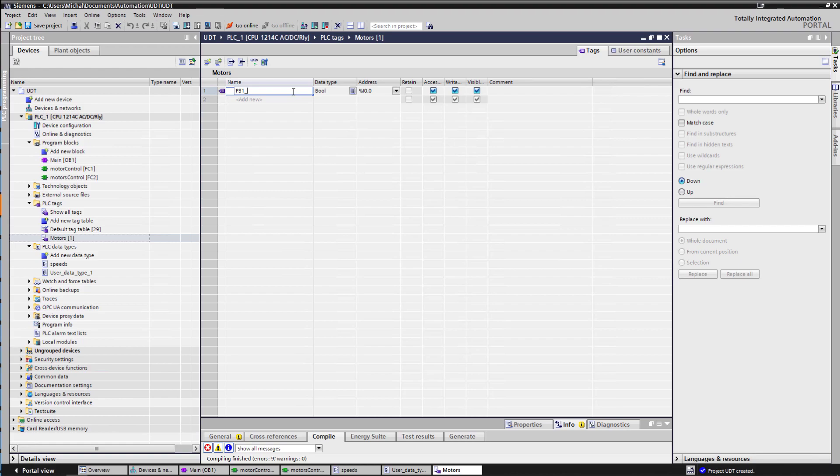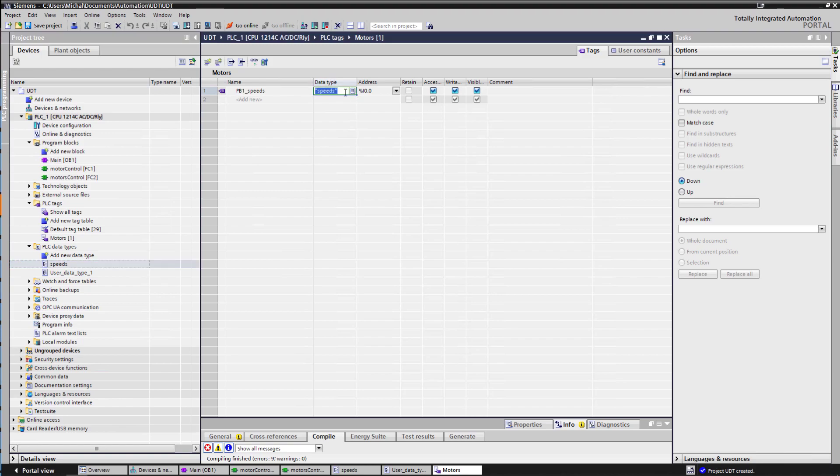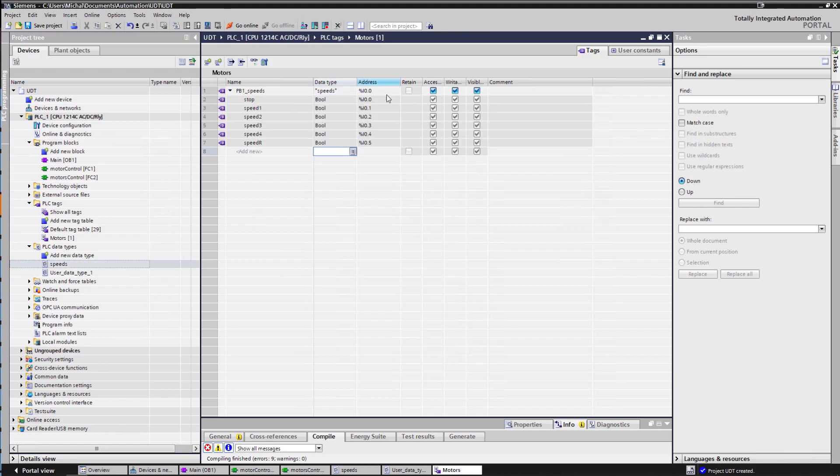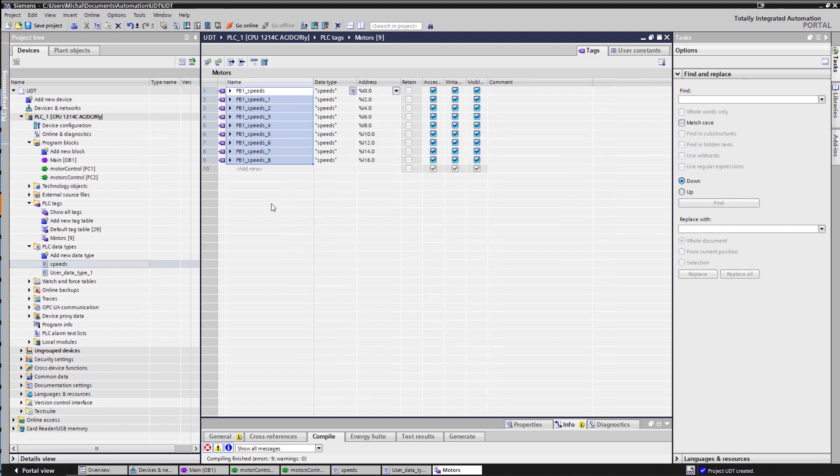So rather than doing this, I would just go, yeah, push-button station 1, speeds, and what is the type? The type is speeds, and as you can see, it maps it nicely for me. It starts with I00, spans however many addresses it needs to span, and I can have multiple of these for my different stations. And I don't worry about things, and again, if I change it, it will get propagated here.